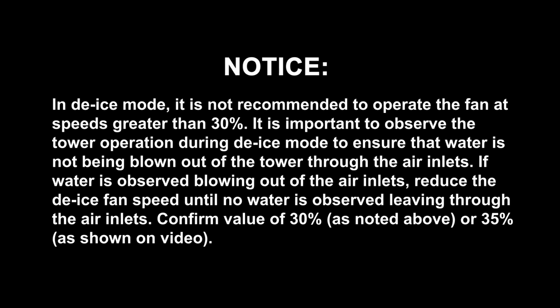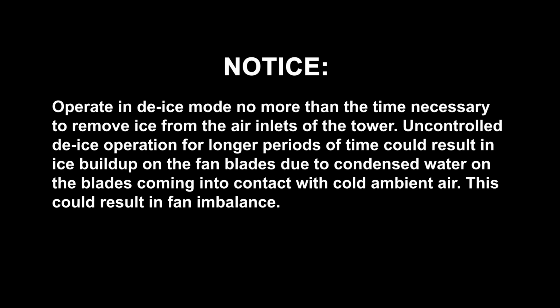Confirm value of 30%, as noted above, or 35%, as shown on video. Also note: operate in de-ice mode no more than the time necessary to remove ice from the air inlets of the tower. Uncontrolled de-ice operation for longer periods of time could result in ice buildup on the fan blades due to condensed water on the blades coming into contact with cold ambient air. This could result in fan imbalance.